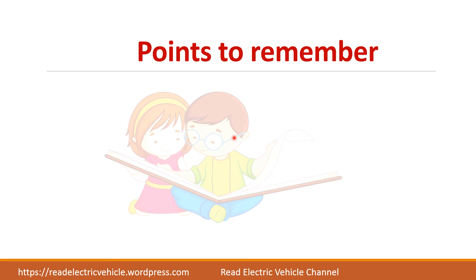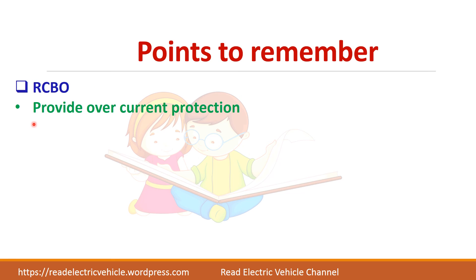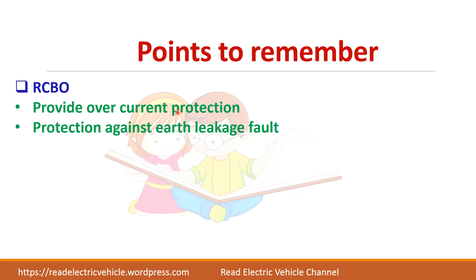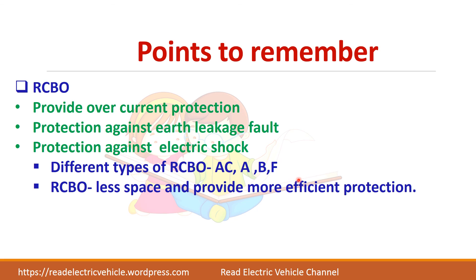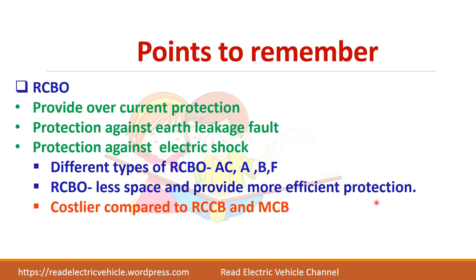The key points to remember are that RCBO can provide overcurrent protection, short circuit protection, protection against earth leakage faults, and protection against electrical shock. Different types are available: AC, A, B, and F. Their advantage is that they occupy less space and provide more efficient operation, whereas they are costlier compared to RCCB.